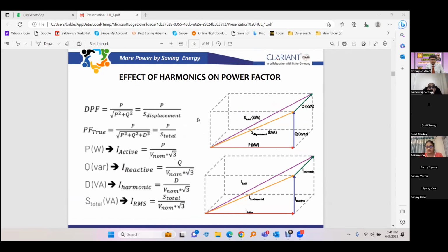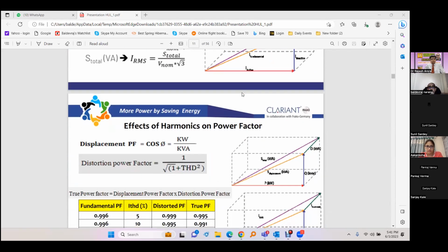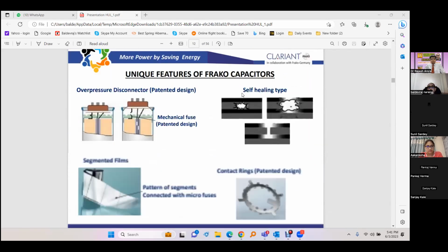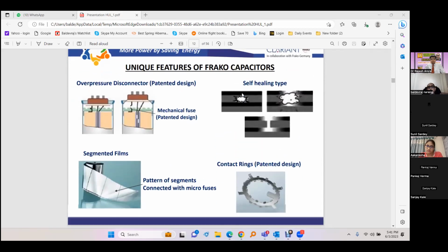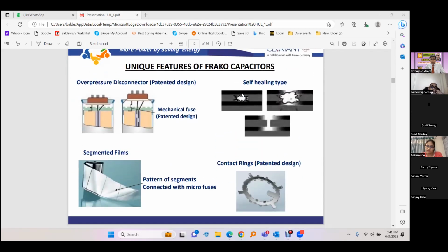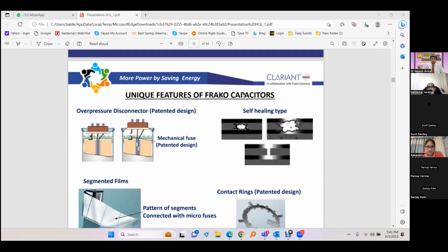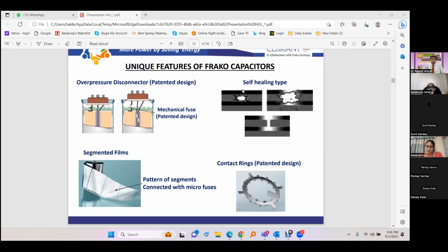Right, sir. I had come up to this slide about the impact of harmonics on the system, the power factor and the reactive power requirement. There is another very important aspect today. All over the world, people are using MPP capacitors for low voltage installations, because of safety concerns. But in India, we still continue to use outdated APP capacitors. That is something I always try to emphasize in discussions.